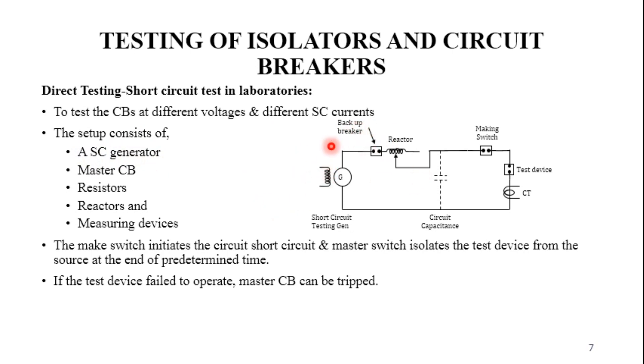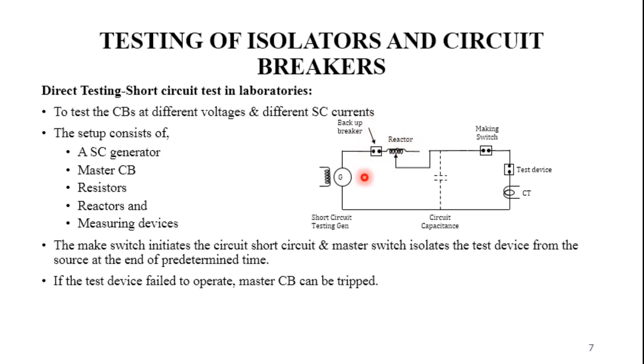The laboratory setup includes a short circuit generator, master circuit breaker, resistors, reactors, and measuring devices connected via CT and PT. The making switch initiates the short circuit, and the master circuit breaker isolates the test device from the source at the end of a predetermined time. Initially the making switch closes, transferring energy from the short circuit generator and reactor to the test device for both high voltage and high current testing. If the making switch cannot isolate, the backup breaker or master circuit breaker comes into action to isolate the circuit from the source.